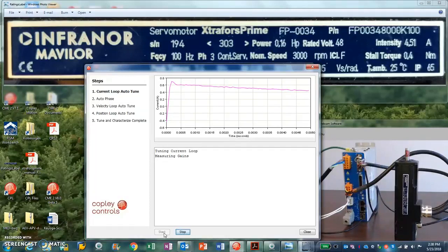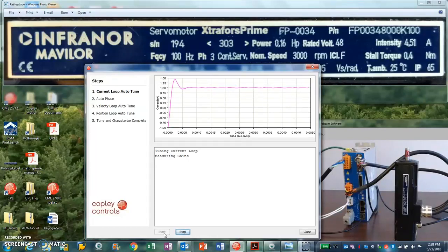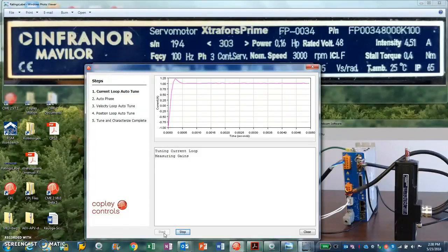It's a ballpark figure, but knowing the winding resistance is always good, especially while the motor still works. Because when the motor stops working, maybe it overheated and the resistance is no longer the original value. So I like to know what that is so that I can check things out when things go wrong. So use an ohm meter to measure the winding resistance.